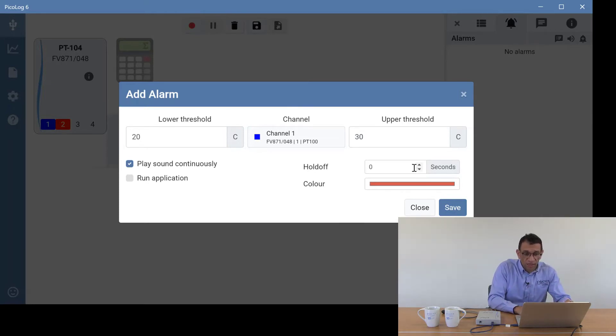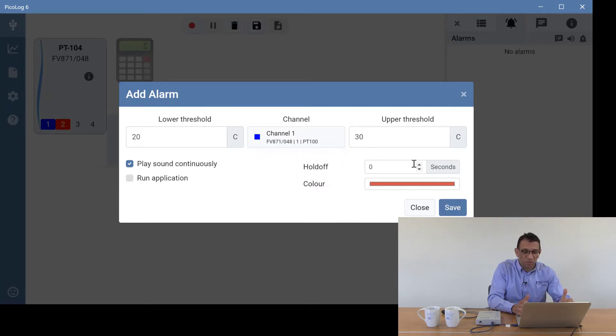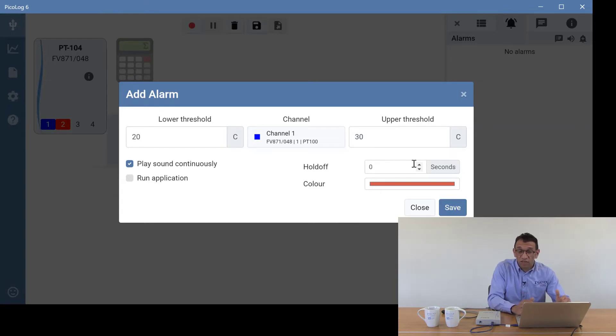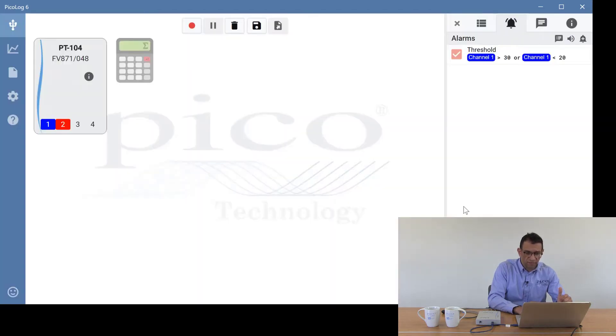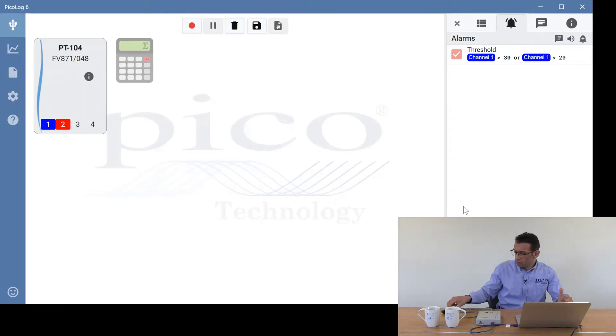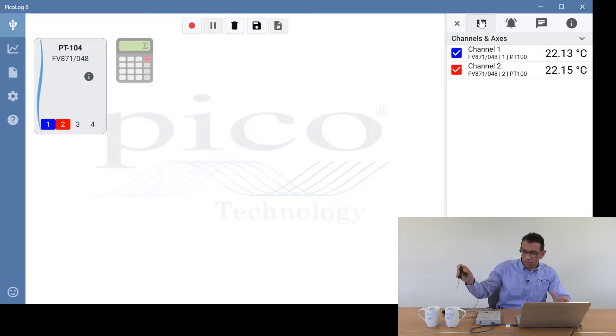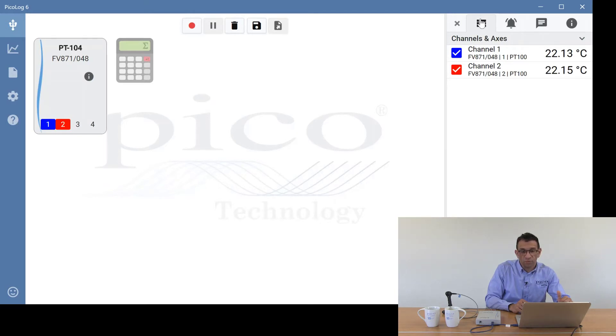The last option is hold off — this is the period of time in seconds between the value going out of range and alarming. This is useful if you have values that occasionally go out of range, for example during a defrost cycle in a freezer. You can also change the color of the alarm notification. Clicking save, we get our probe and put the temperature probe in the cold mug and wait for it to alarm.